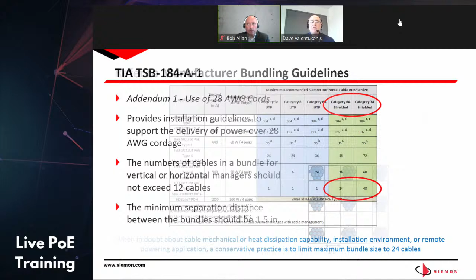Even if you look at type 4 with a maximum ambient temperature of 45 degrees C, which I think is suitable for many customers, you can get up to 24 cable bundles even with category 5E and 6 and 6A UTP as well. So that 24 is a good number. If you just don't know, it's a great general practice rule to apply across your designs, and then you don't have to give as much consideration to the rest of the installation.